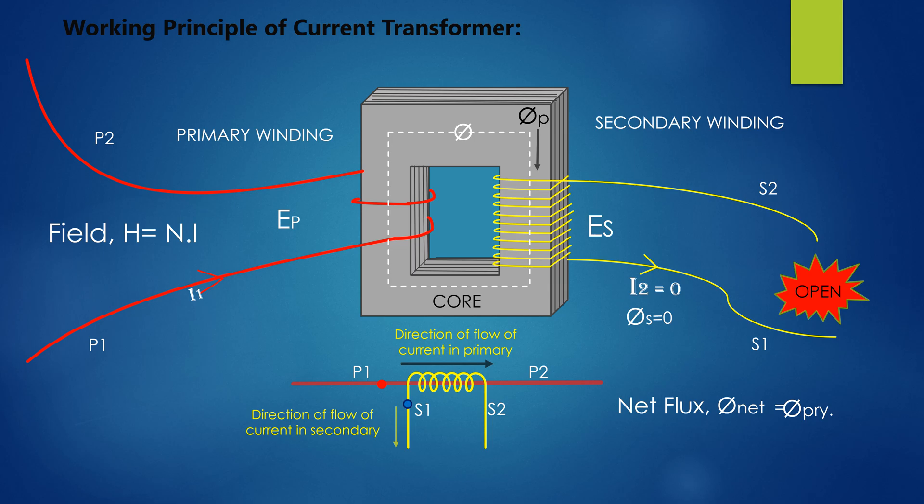Hence, huge flux linked with primary winding due to flow of high primary current, in absence of secondary current, is the net flux which is totally engaged to induce voltage at the windings by electromagnetic induction. Due to absence of flux in secondary, net flux, that is primary flux, increases to a high value. As the working net flux increases, secondary voltage increases to a high value and core gets saturated.